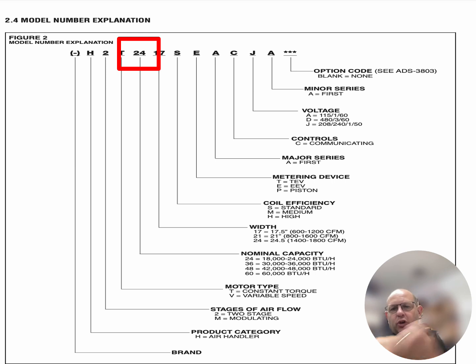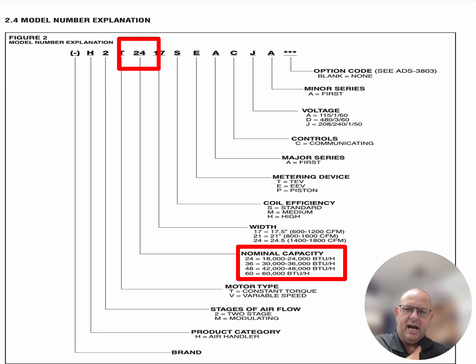Now, as we continue to look at this system, let's go ahead and highlight what I'm really concerned about, the nominal capacity. So we see 24. Now, if you don't have the breakdown of the actual unit, just look for multiples of 12. Well, 12, 18, I know 18 is not a multiple of 12, but 12, 18, 24, you're going to see these numbers sitting inside of the actual model number itself. So we can pick at it and see what the capacity of the unit is without actually looking up the breakdown of how the manufacturer is giving the capacity of that unit.